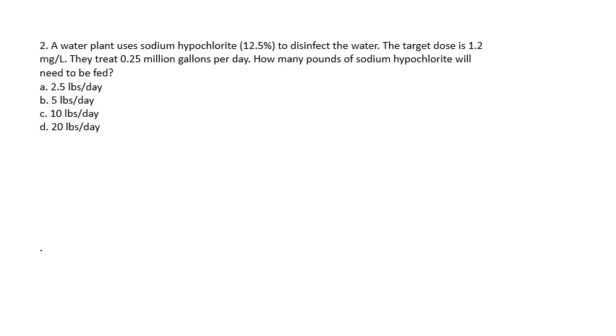Question number two. A water plant uses sodium hypochlorite at 12.5% to disinfect the water. The target dose is 1.2 milligrams per liter. They treat 0.25 million gallons per day. How many pounds of sodium hypochlorite will need to be fed? A: 2.5 pounds per day. B: 5 pounds a day. C: 10 pounds a day. Or D: 20 pounds a day. Pause if you're going to work through it yourself.